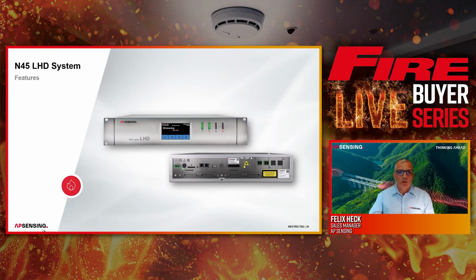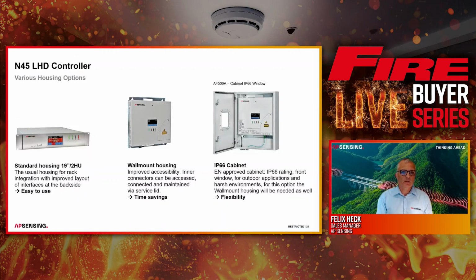Let's speak a little bit about the system itself, about the controller, as you can see here. We provide different housings. This is important for the flexibility of your project. The standard housing is the 19-inch, 2 height unit housing that can be integrated into the cabinet with a fire panel. But we also provide a wall mount housing, which can be easily installed directly on the wall in the technical area somewhere. And if it is not possible, or if you do not have a technical area, then we can also install an IP66 cabinet somewhere in the field, wherever it is necessary, very close to the conveyor, or somewhere else in the production, for example.